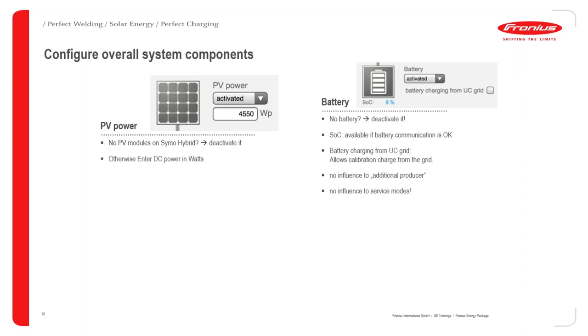So for the PV power, if there's no modules, some people may be using the hybrid inverter in an AC coupled mode, so you may have a grid connected inverter already there and you just want to add the battery, so you're adding just the hybrid with the battery connected. Then in this case you would deactivate the PV power, but I believe in most cases in Australia at the moment you will have panels directly connected to the hybrid. So you activate it and you put in the amount of DC power you have connected to it. So not the AC power rating of the inverter, but the DC that you've got connected to it, in watts as well and not kilowatts. So yeah, if you're not using it, you deactivate it, and then you've got the battery.